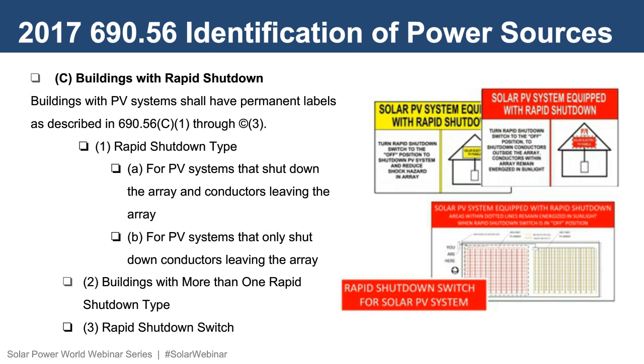If a building has more than one rapid shutdown type installed on it, a detailed plan view showing which arrays are controlled by which type of rapid shutdown must be installed.